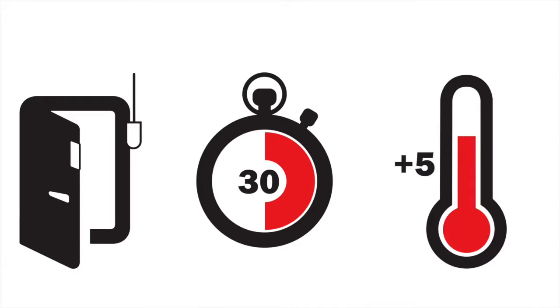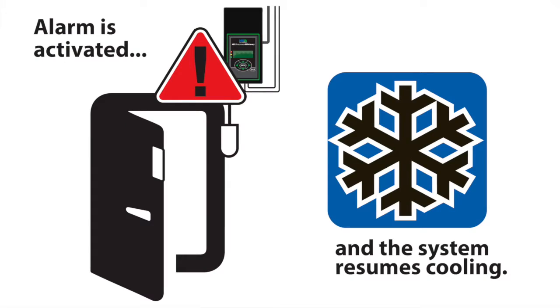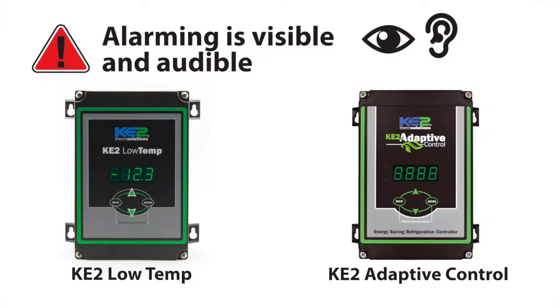The further benefit of the door switch is the ability to trigger an alarm. When the door alarm delay is exceeded — the default is 30 minutes — and the temperature in the space rises, an alarm is triggered. When the system goes into alarm, the system is turned back on to resume cooling to protect the perishable product.